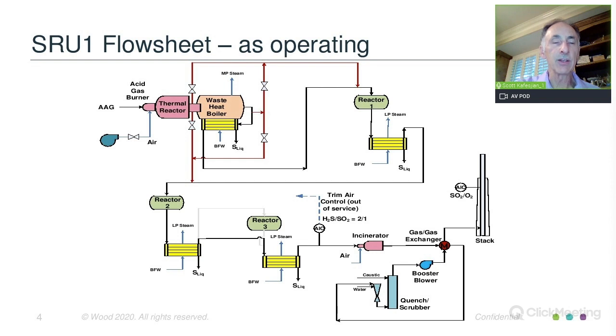The interesting things here and some of the difficulties were, first, the reactor reheat scheme uses a very difficult configuration called hot vapor bypass, where the 2000 degree gas from the thermal reactor or roughly 1,000 degree F gas are mixed with the inlet to the reactors to bring them up to temperature. Very difficult service and difficult control.